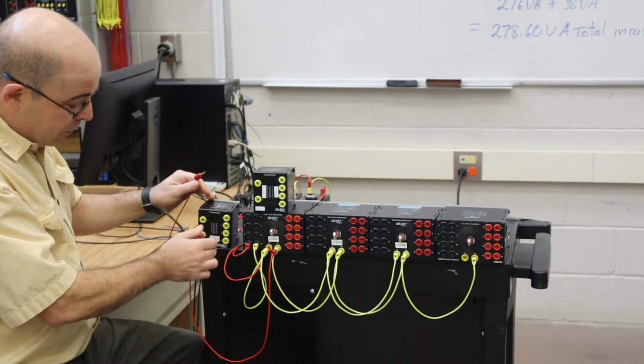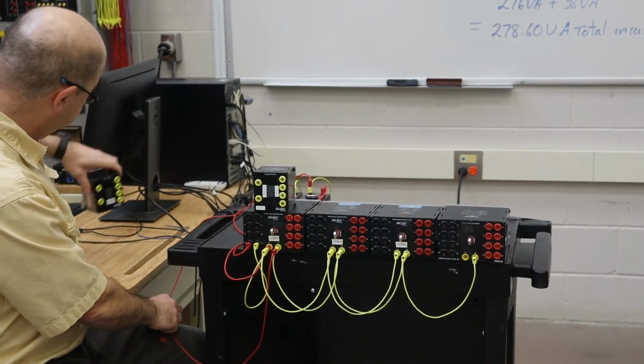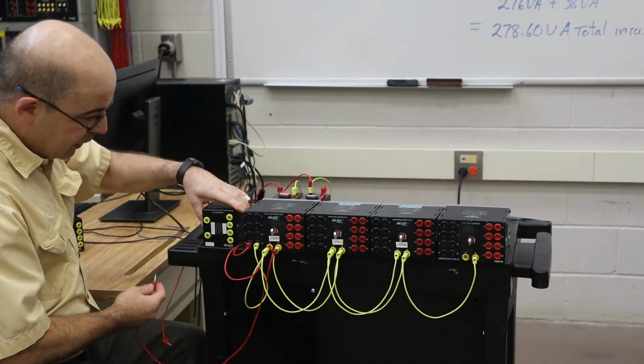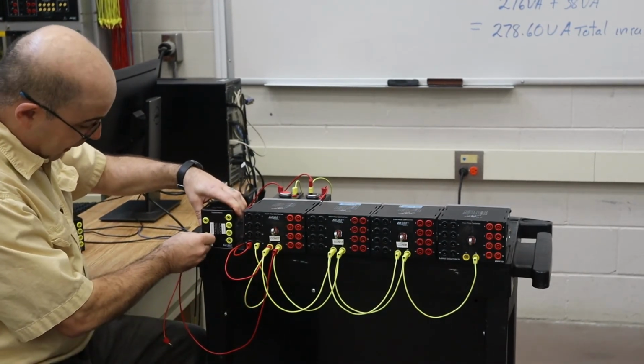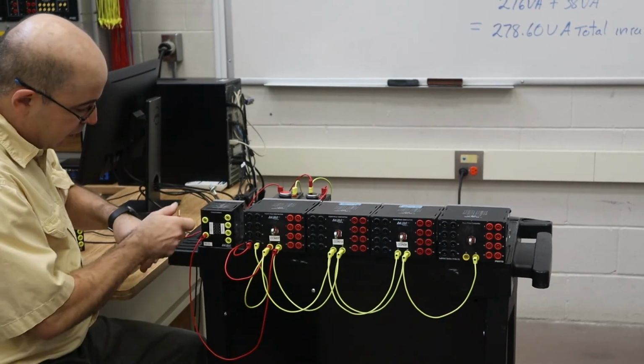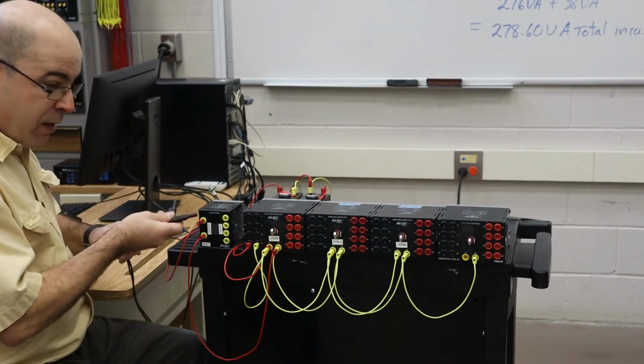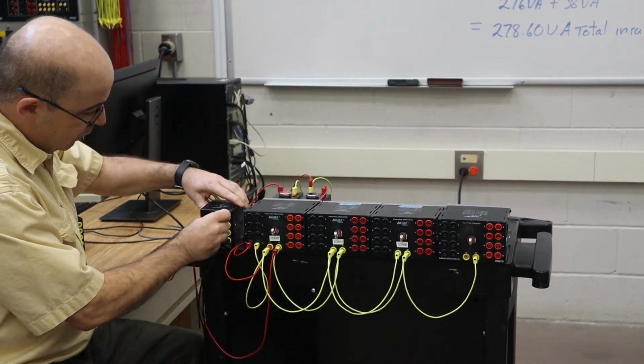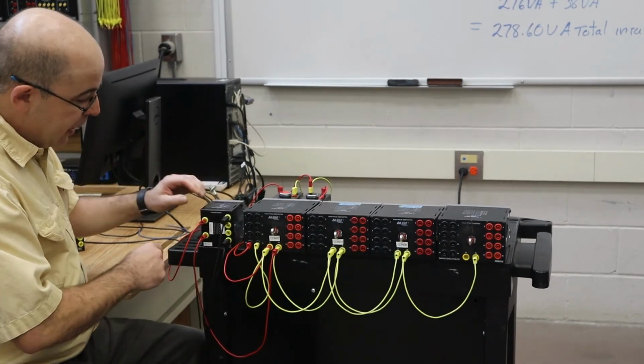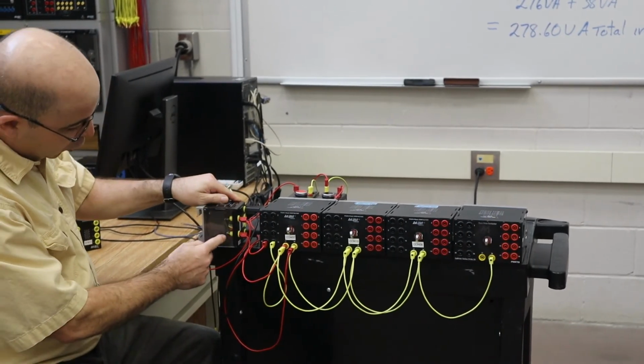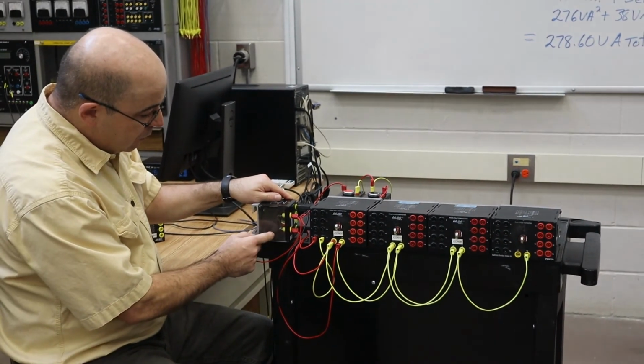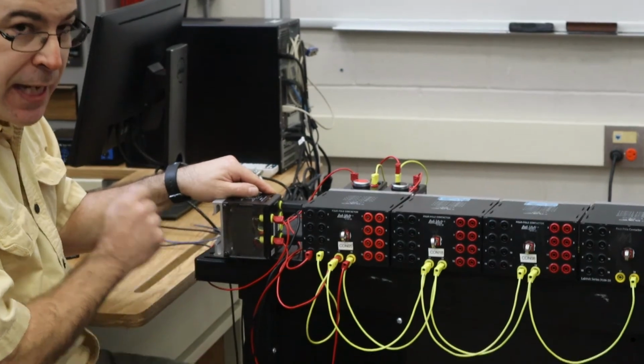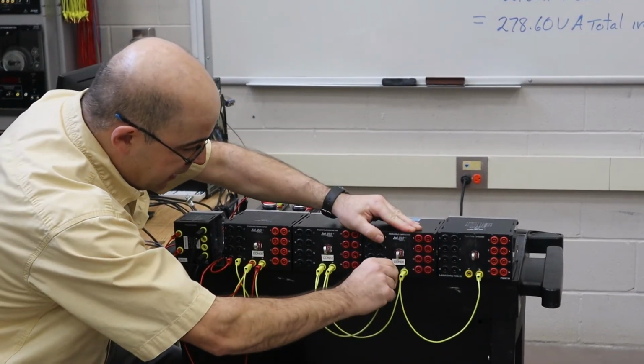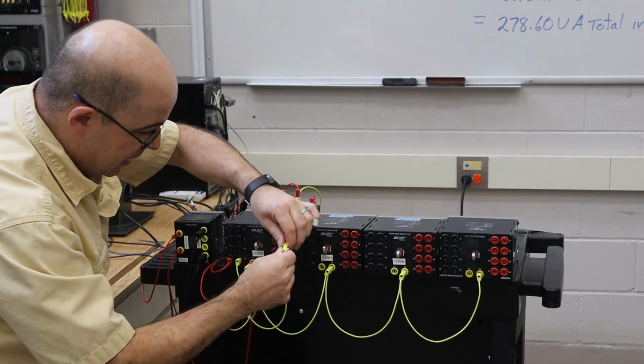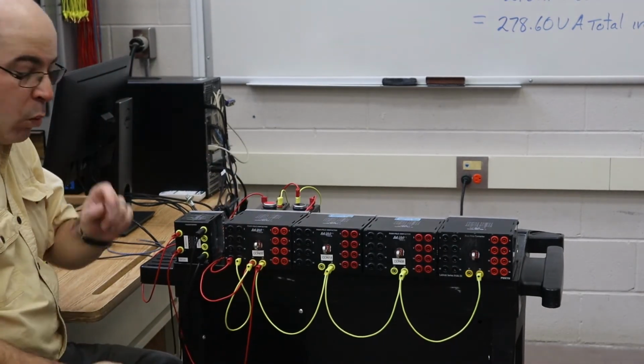So the first thing, I've already taken apart the input power. And so we're going to wire up the secondary. So this is going to the neutral, or X2. Up here, this is going to go to my push button station. And finally, we're going to power things up for 208 volts. Now, you can see that I've got the larger core. So I genuinely have a 50 VA control transformer in my circuit. So I want to pick up where we left off, and I'm just going to strip out these leads, and we're going to start off again with one relay.